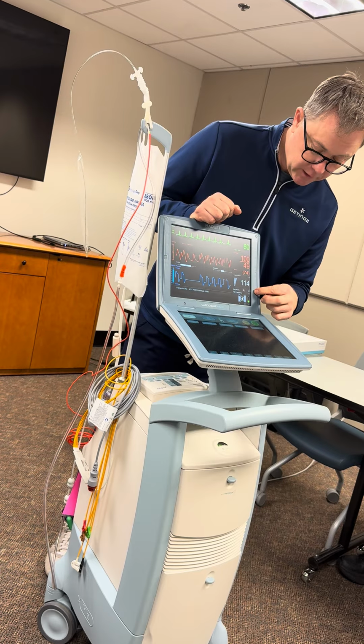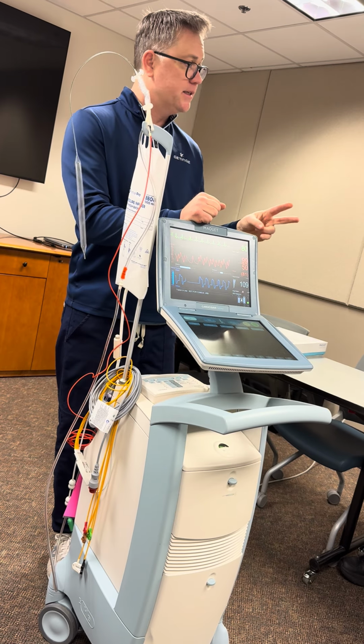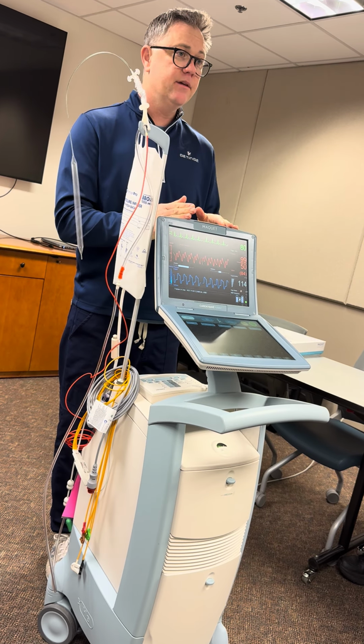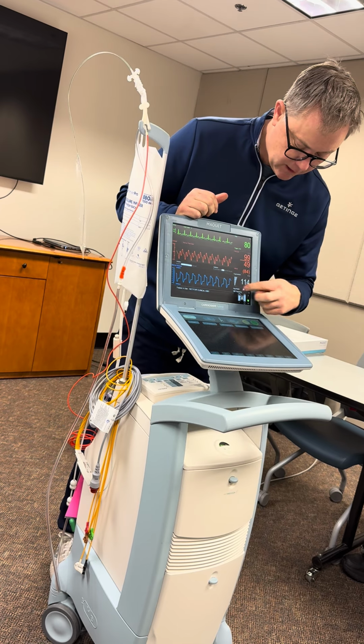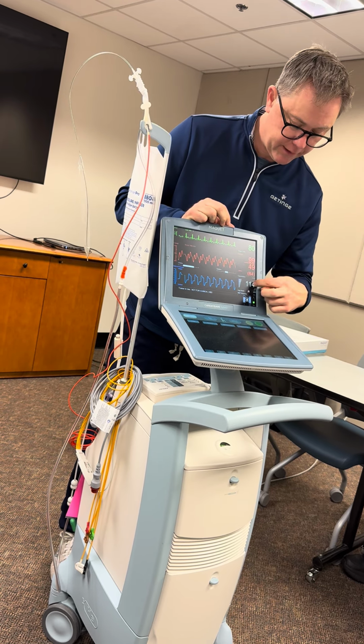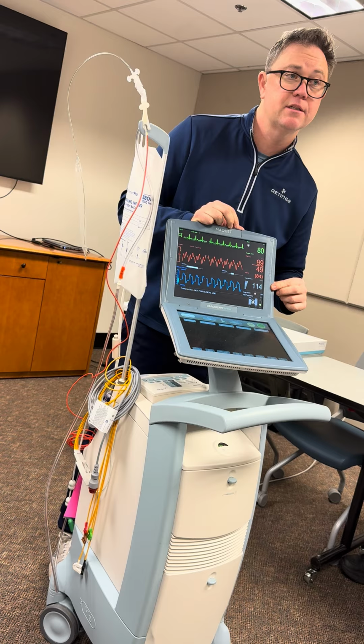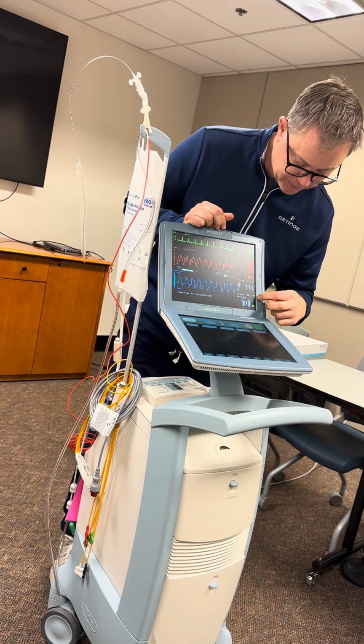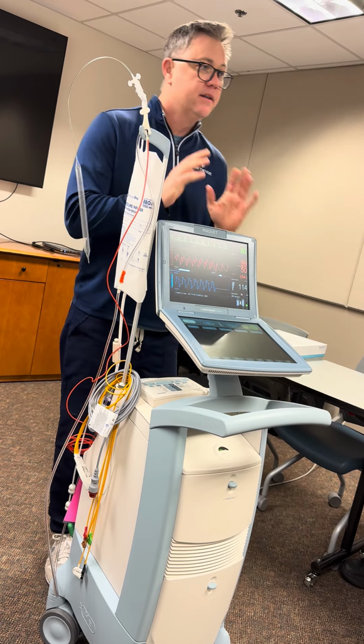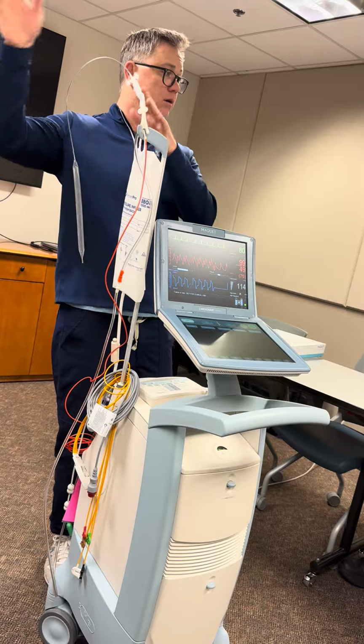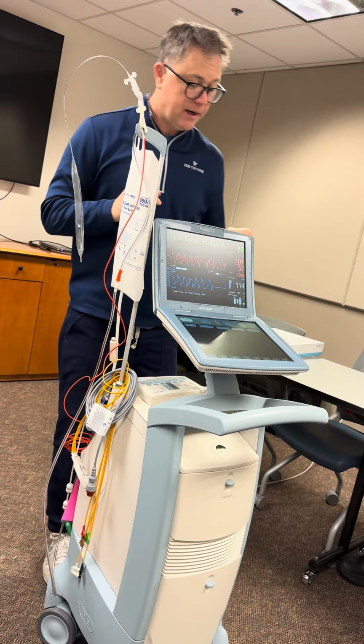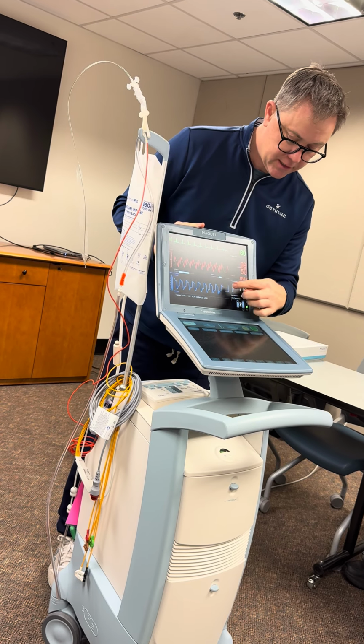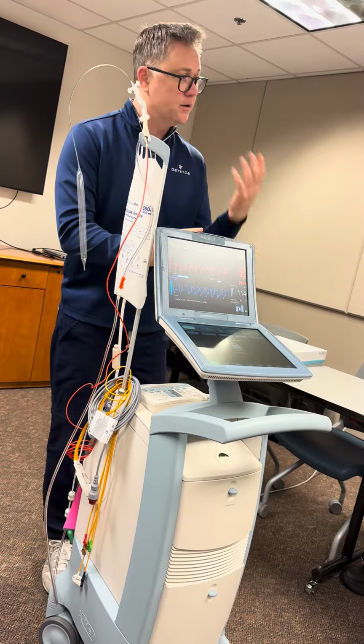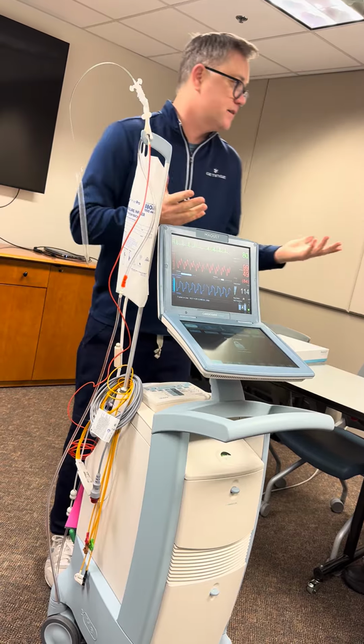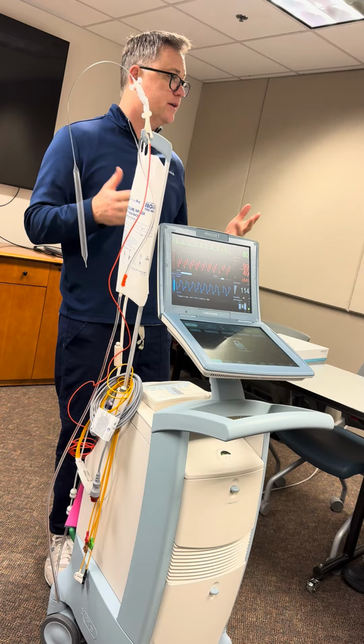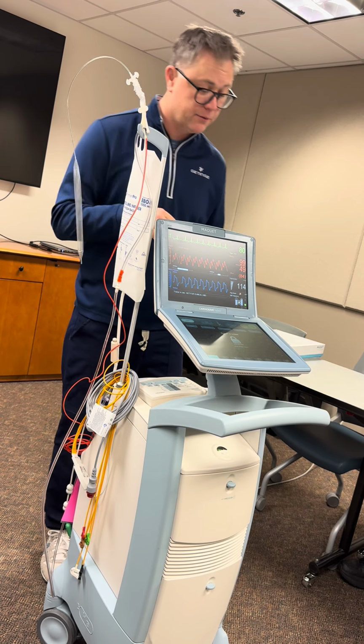Balloon pump will set what's called an augmentation alarm 2 minutes into the case. So it's going to learn this patient's rate and rhythm, and then it will set this augmentation alarm roughly 10 below whatever their diastolic augmentation number is. So it'll, in a second here, probably set this at about 104. This is really not an alarm for the cath lab. It's more an alarm for the ICU. If the patient's heart rate changes, our diastolic augmentation will crash. It will trip that alarm, and it's basically just telling them, hey, my heart rate's changed, come check on me. It's a come check on me alarm for the ICU.